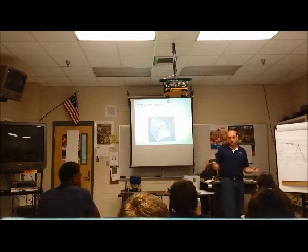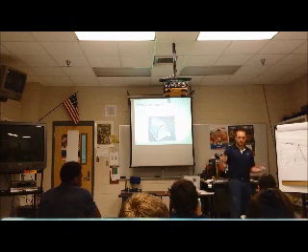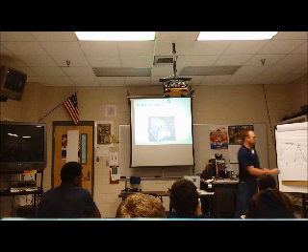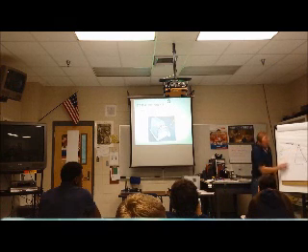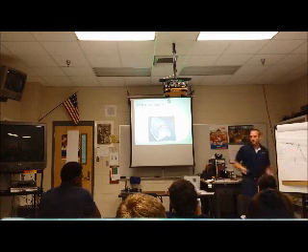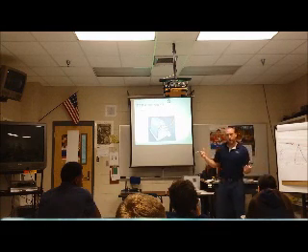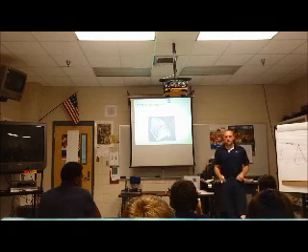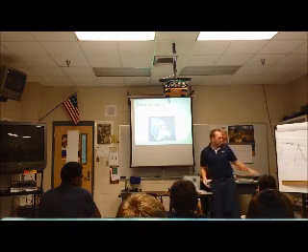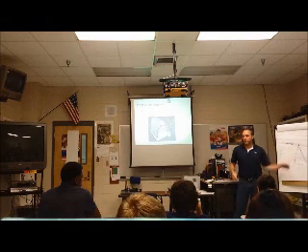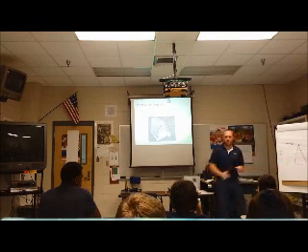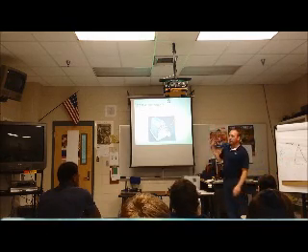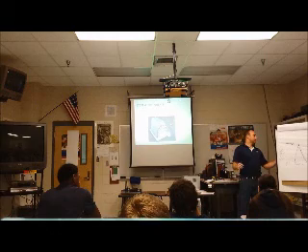That's pretty neat. That's getting into the refrigeration cycle head on. So when the air flows through here and it's say 88 degrees, the refrigerant soaks the heat in, and then the air feels a little cooler, 79. So that changed 9 degrees just by going across the evaporator. Everybody see how that's working? So if I say, what is an evaporator? It is a heat exchanger.